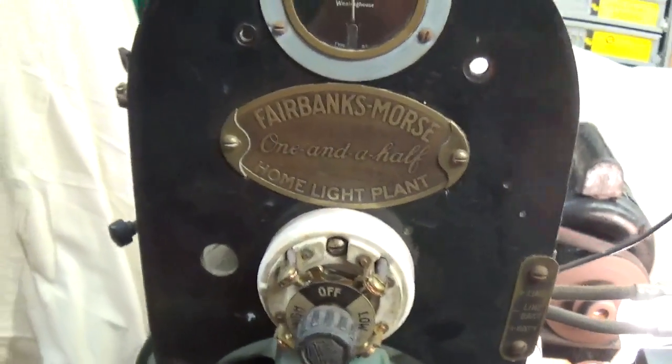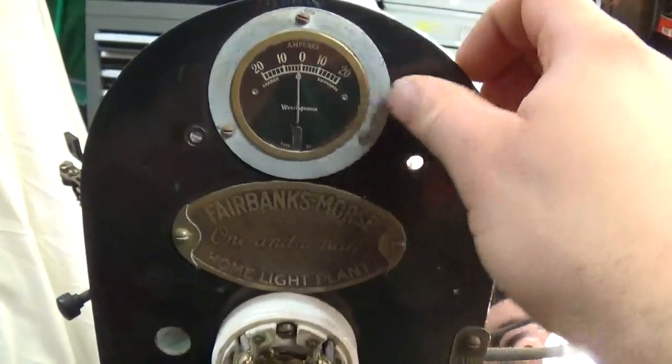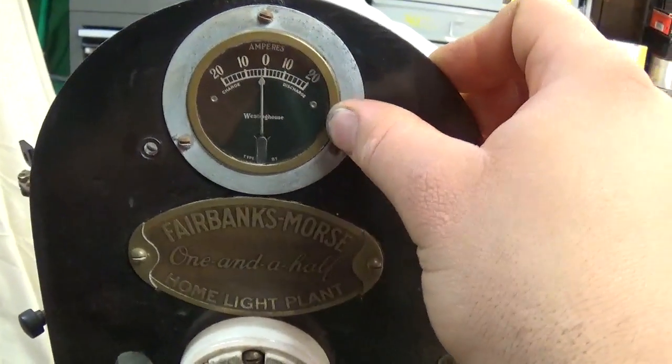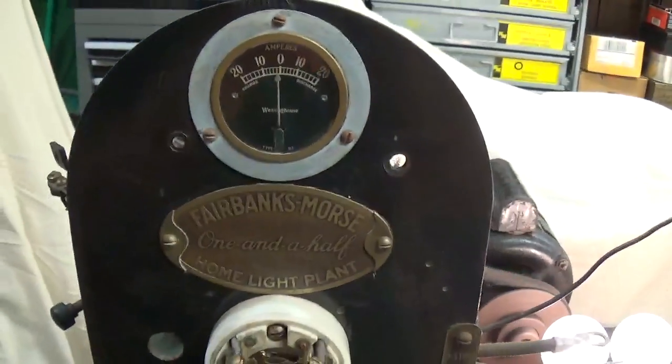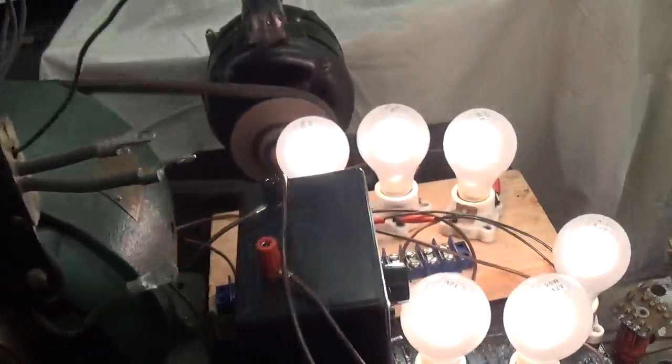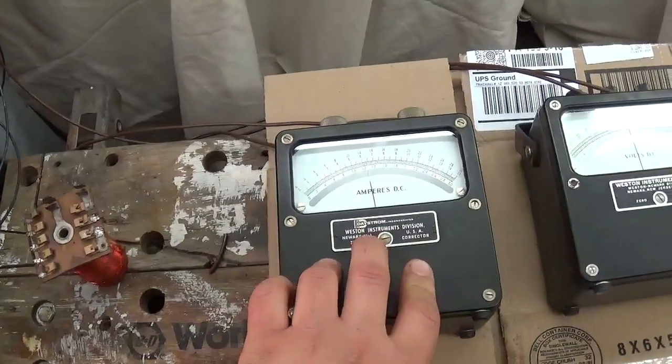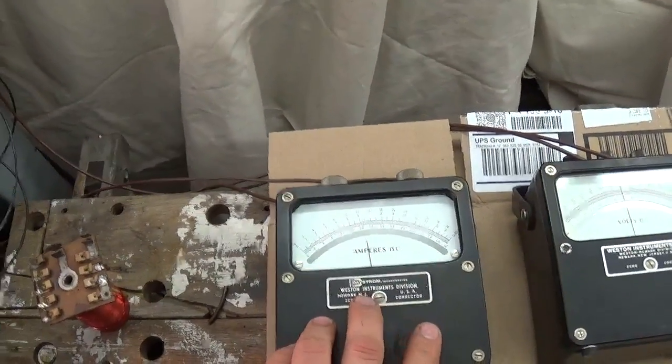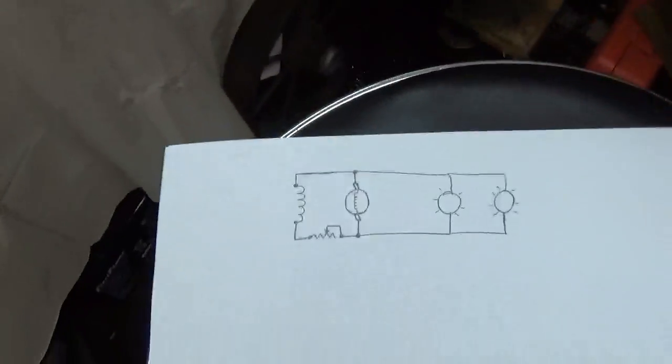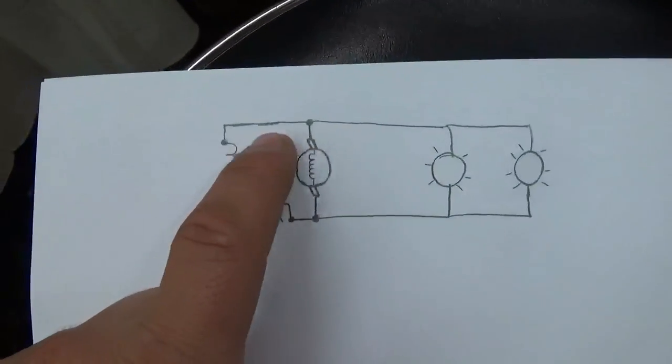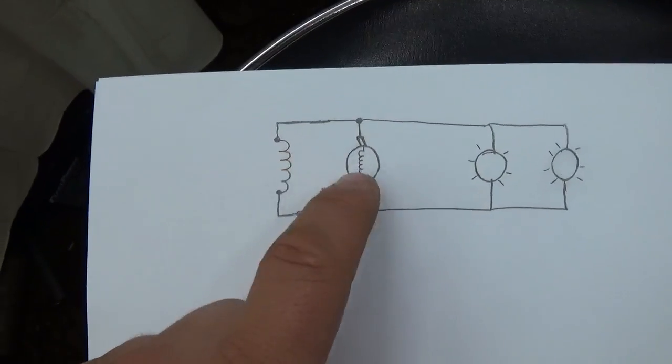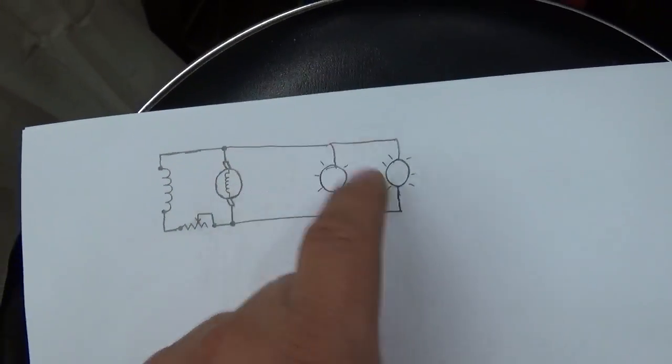So Fairbanks-Morse, one and a half. I could probably just set this meter up so that it'll just show whatever current the unit is drawing. Like I said, this meter is measuring field current, not load current. So in the diagram, the meter would be here in between the field and the armature, and not here between the load and the output.